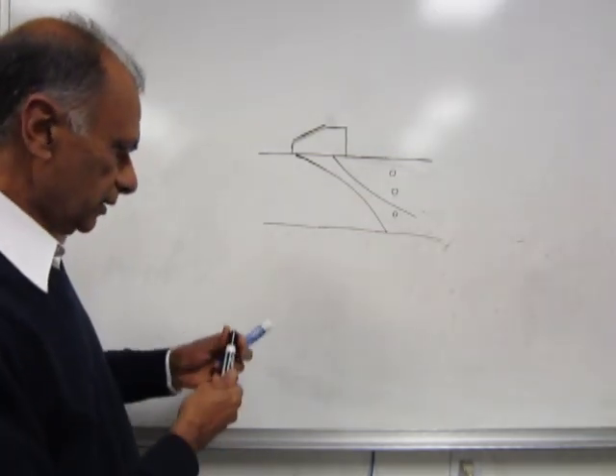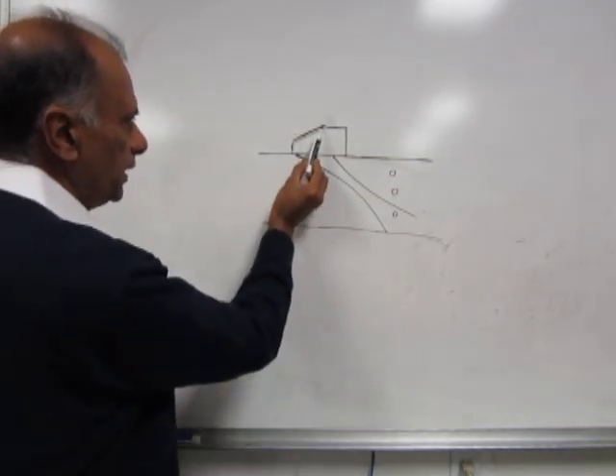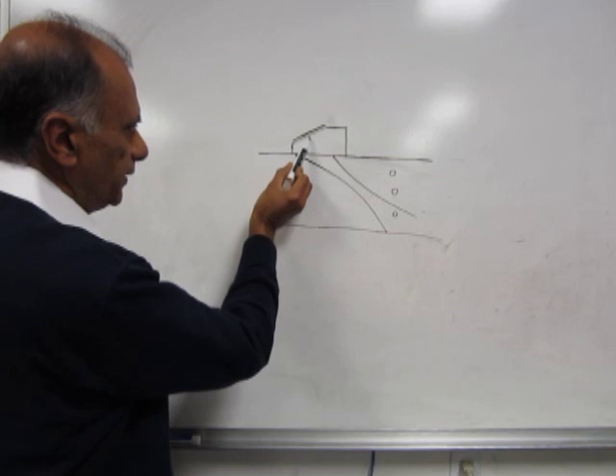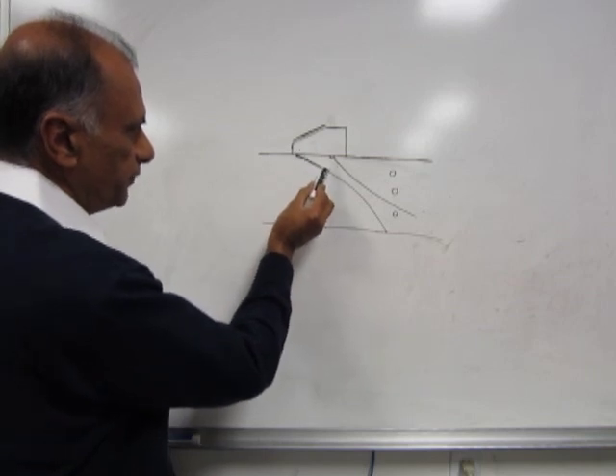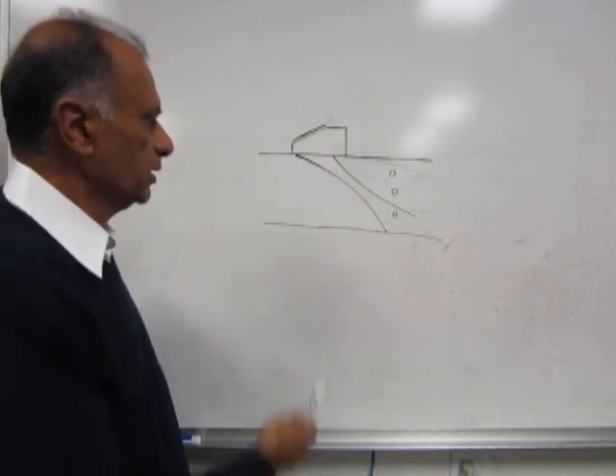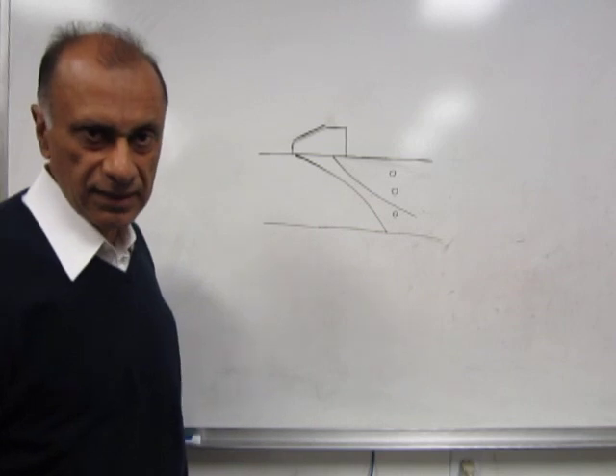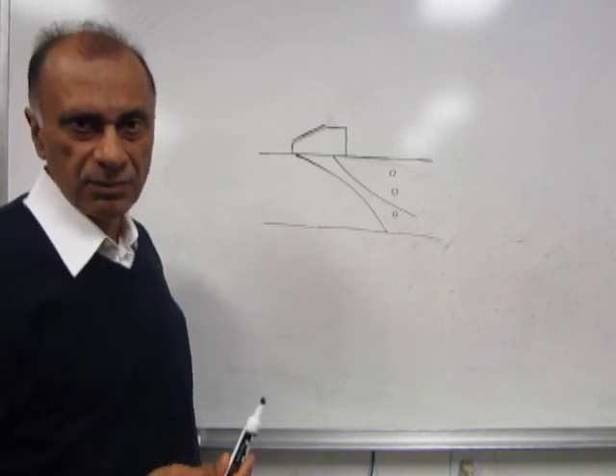On the angle beam probe we basically have a piezoelectric crystal here that transmits L waves. They are refracted into shear waves and it produces a shear wave beam, for example at a refracted angle of say 60 degrees, and the beam has a beam spread.